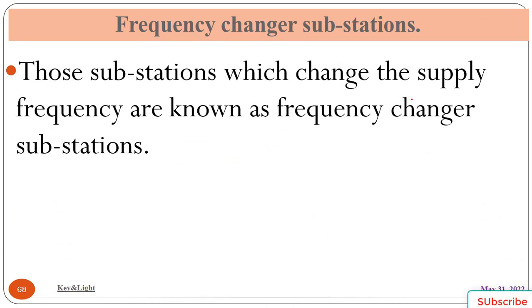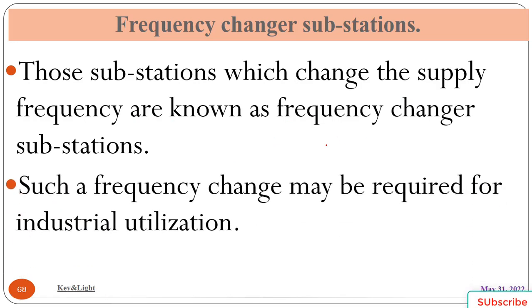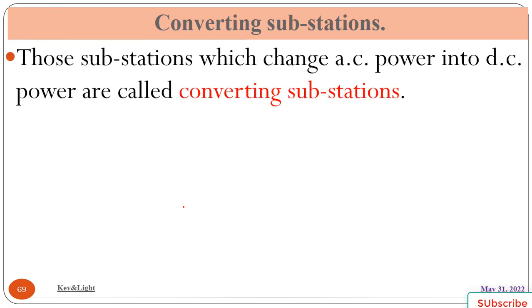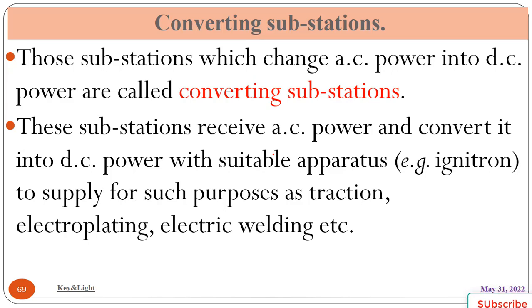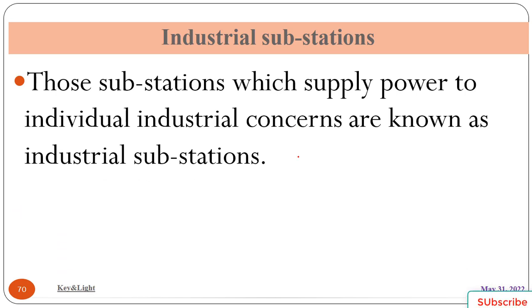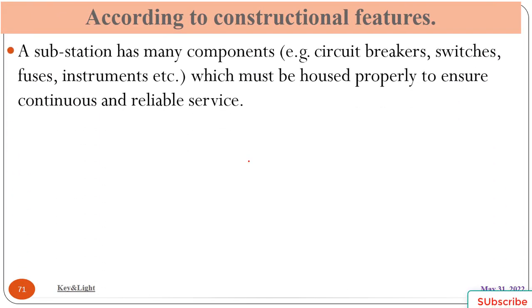The next one is frequency changer substations. Those substations which change the supply frequency are known as frequency changer substations. Such a frequency change may be required for industrial usage. Converting substations, as the name indicates, are those substations that change AC power to DC power. These substations receive AC power and convert it into DC power with suitable apparatus, for example, ignitron, to supply for purposes such as traction, electroplating, electric welding, etc. The next one is industrial substations. A substation which supplies power to individual industrial concerns is known as an industrial substation.